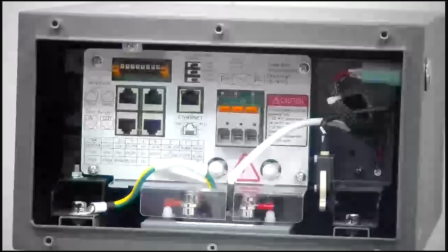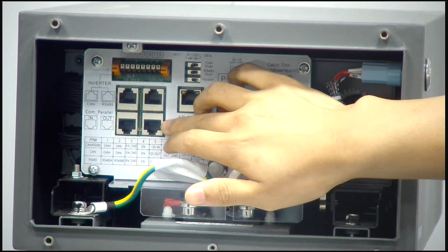Okay, so inside the BCU, the whole side cover was removed. There are some spots you should notice. First is here, this part. Below these 2 connection parts is the communication cable connecting place between batteries, so if you have a parallel system, you need to use this part. For the top, this one and this one here are for the communication between the battery and the inverter.